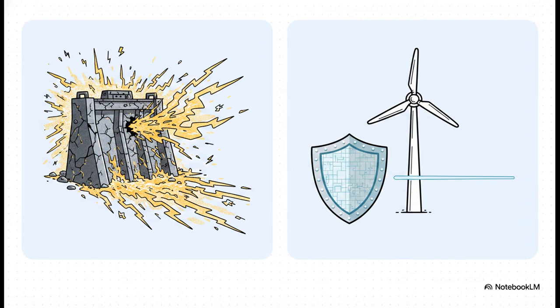Unlike those old iron giants we just talked about, a Type 4 turbine's generator is completely physically isolated from the power grid. Between the turbine itself and the grid sits a massive array of power electronics. Think of it like a highly trained traffic cop facing down a flash flood. While the old generator bursts like a broken dam, the modern Type 4 turbine uses its power electronics to act as a strict digital firewall, meticulously buffering and regulating the flow of electricity.